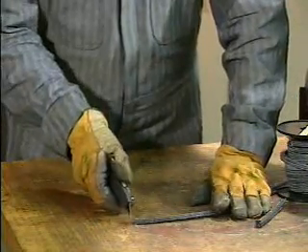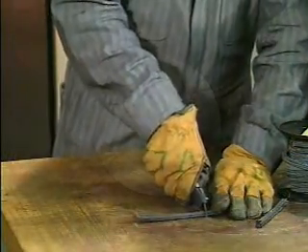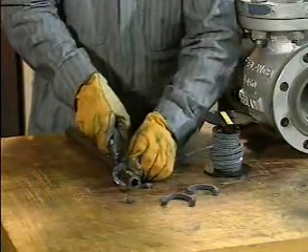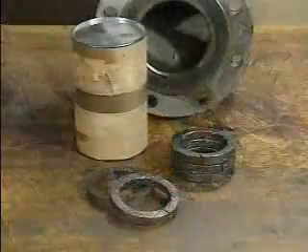the first ring. This method is not always effective for larger valves with thick packing. Often a small V-groove is formed at the adjoining ends because the packing isn't curved when it's cut. The V-groove would allow packing leakage. To avoid the V-groove problem on larger valves, wrap the packing around a mandrel and then cut it.